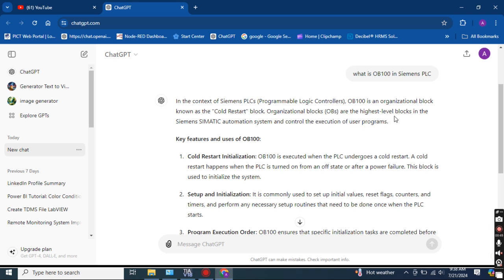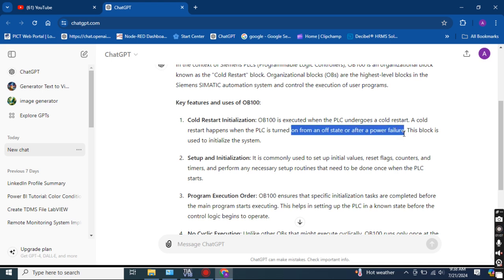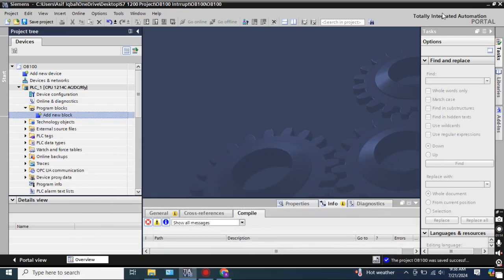Organization blocks (OBs) are the highest level blocks in the Siemens automation system and control the execution of the user program. OB-100 is executed when the PLC undergoes a cold restart — this happens when the PLC is turned on from an off state or after a power failure. So this OB is executed whenever your PLC is restarted or powered on from the off position, or after power is restored.